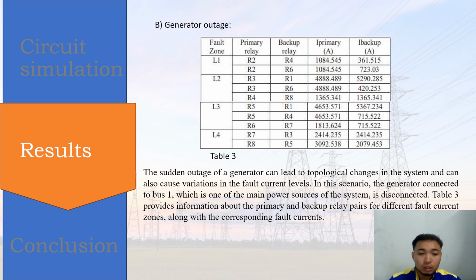Generator outage. The sudden outage of a generator can lead to a topological change in the system and can also cause variation in the fault current level. In this scenario, the generator connected to bus 1, which is one of the main power sources of the system, is disconnected. Table 3 shows the information about the primary and backup relay pairs for different fault current zones, along with the corresponding fault current.